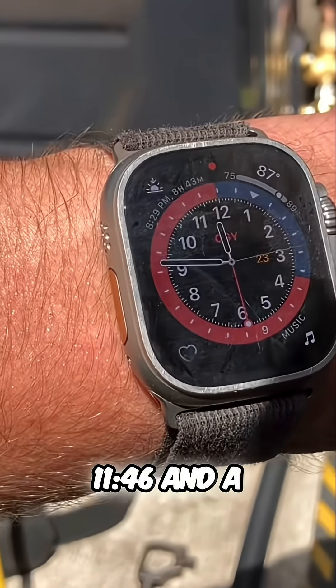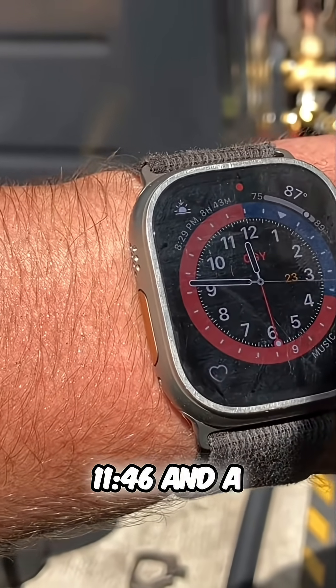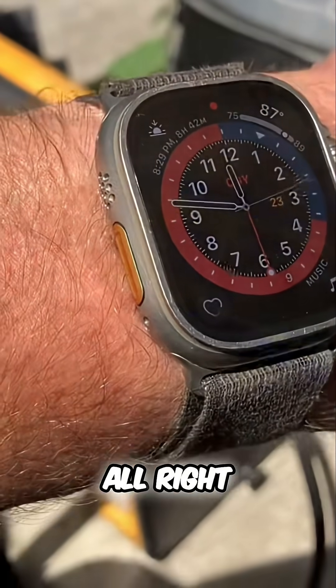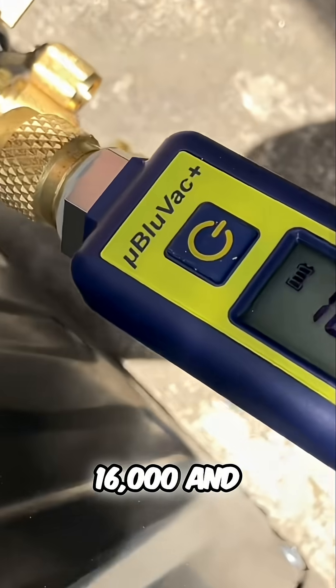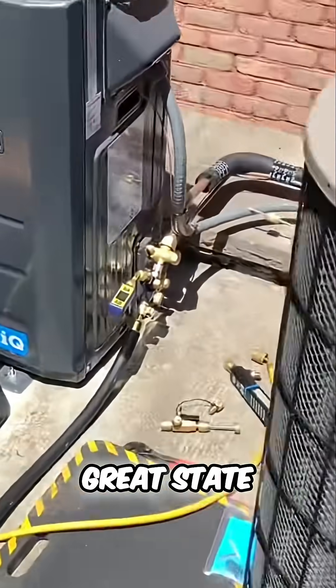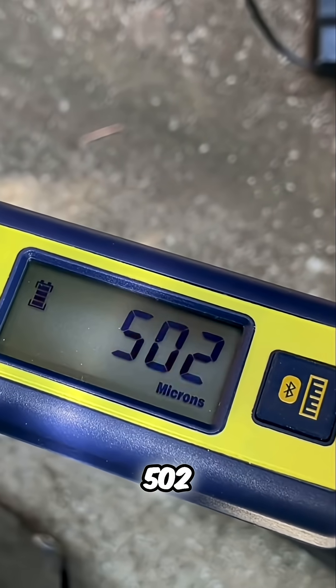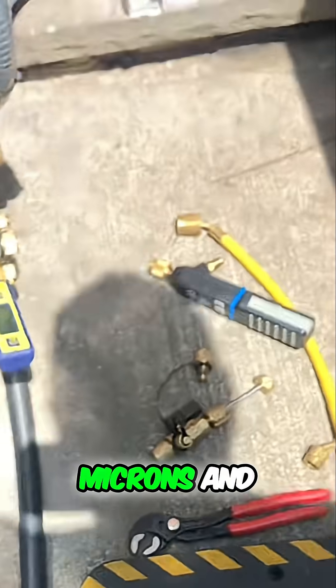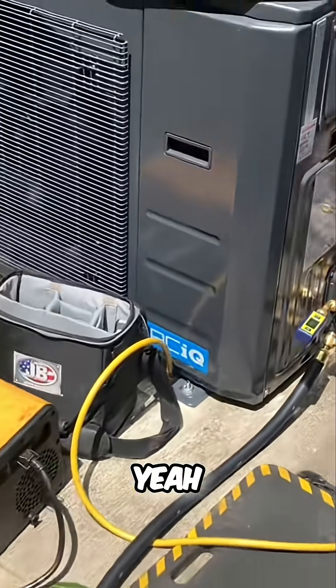It's 11:46 and a half. It's been about a minute — we're at 16,000 and dropping. It's a minute to 12 here in the great state of New York. We are at 504, 503, 502, 501 — we're at 500 microns and still dropping.